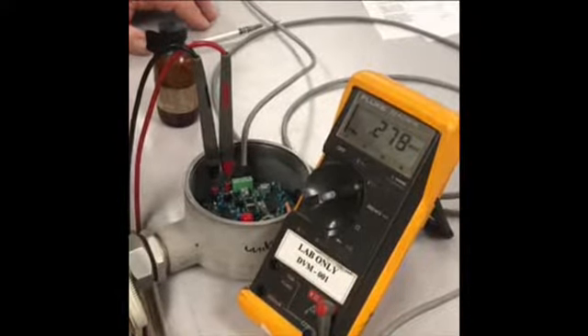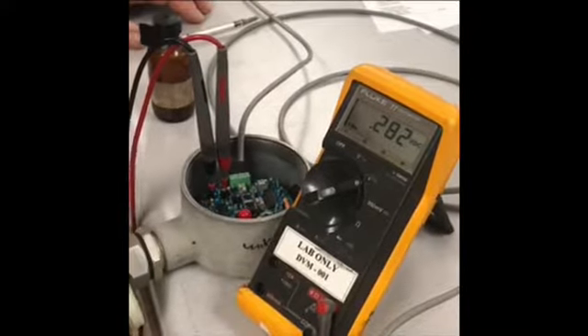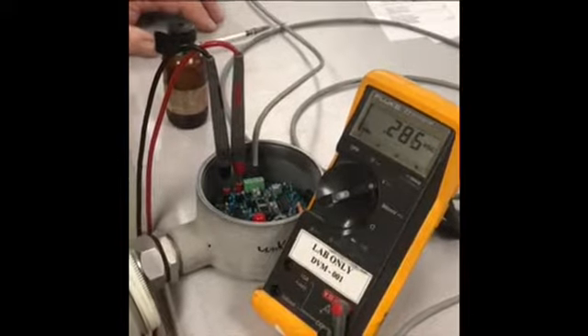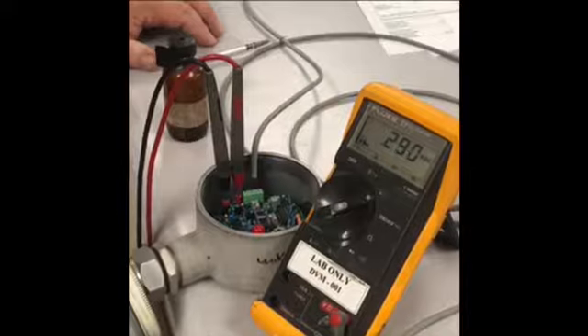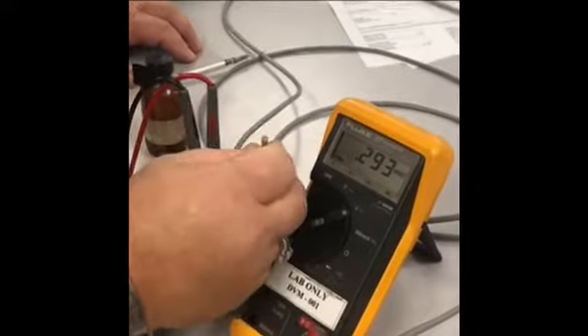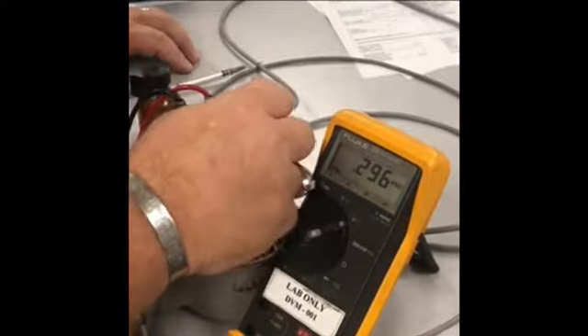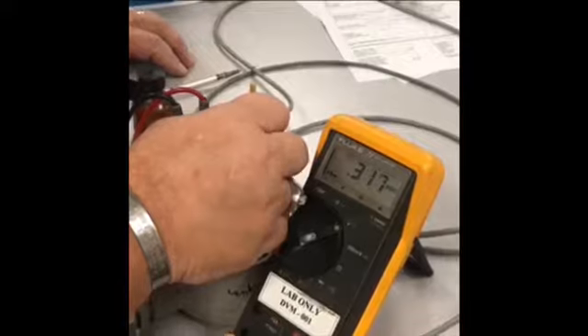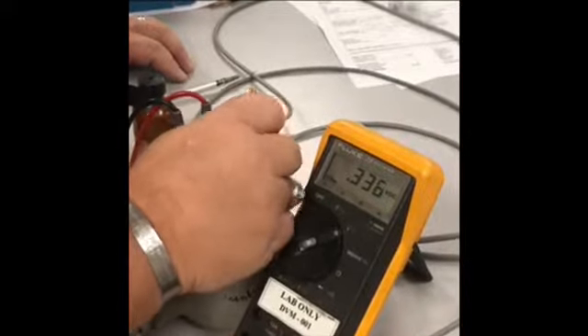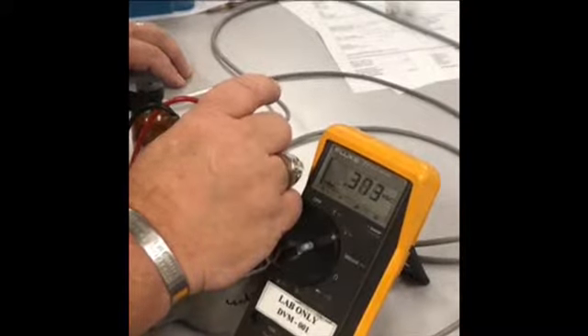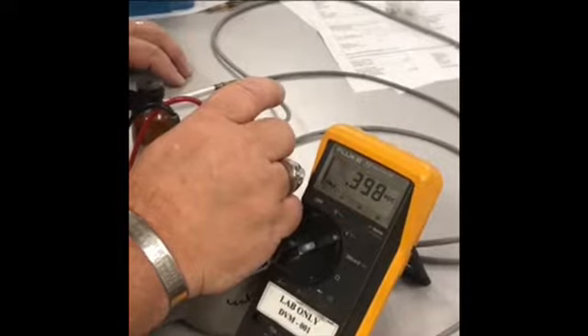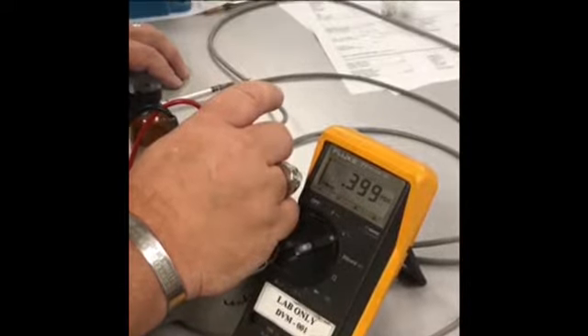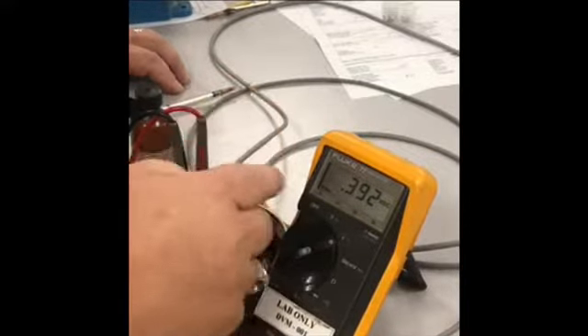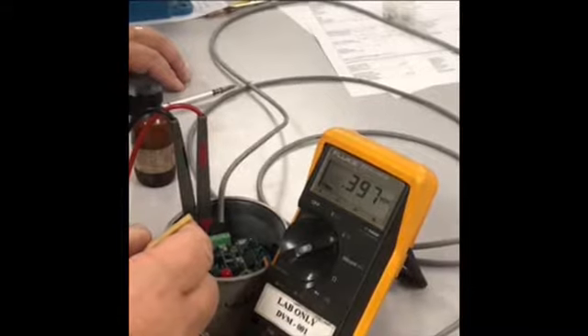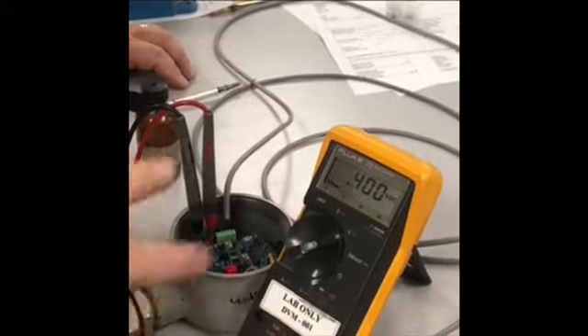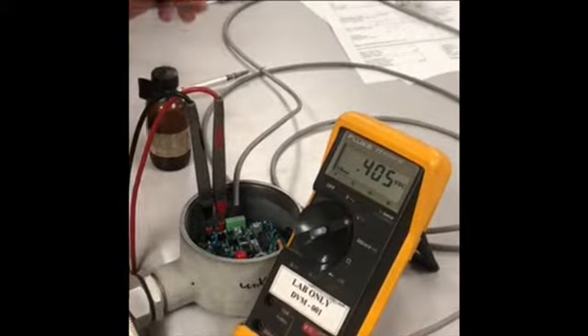As you can see, we're not quite there yet. It's slowing down considerably. I would still let it go beyond this, but for the sake of not having such a long video, I'm just going to go ahead and show you that you can take your screwdriver, put it on the potentiometer, and slowly turn it up to 0.4 volts. 0.4 volts is a full scale reading. Once you have 0.4, you can go a little bit below that. You can see that it's going to go ahead and keep ticking up. Go to 0.4. If it's very slow like that, or even slower than that, you can consider that a stabilized reading.